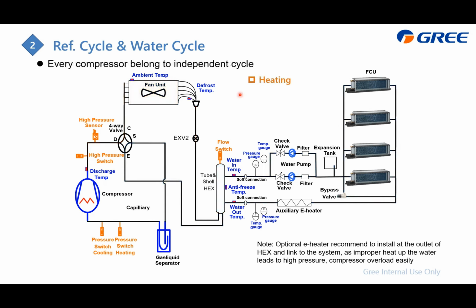This time it is the heating cycle, and the structure, which is the chiller and also the water system, has no change. What's different is we just change the direction on the four-way valve here. And here is how the refrigerant flows. The gas from the compressor will first flow to this shell and tube heat exchanger to release heat, which is heating up the water. Then the refrigerant itself will become liquid and flow to this EXV and get expanded. Then the refrigerant becomes low pressure and low temperature liquid, and goes to the outdoor heat exchanger to absorb heat. Then it will become gas and flow to the gas liquid separator, then to the compressor.